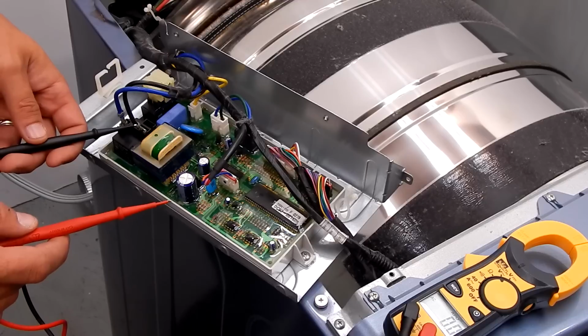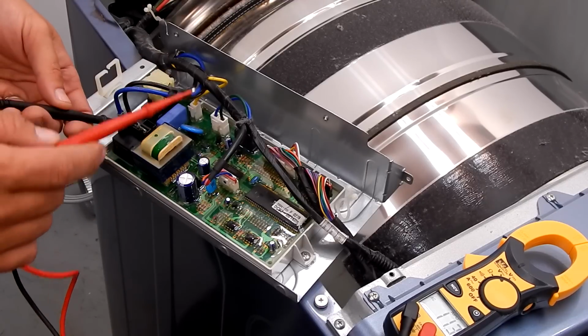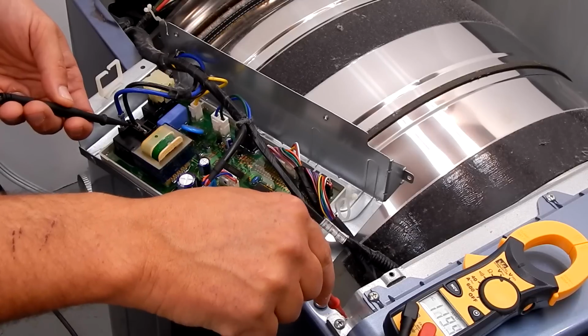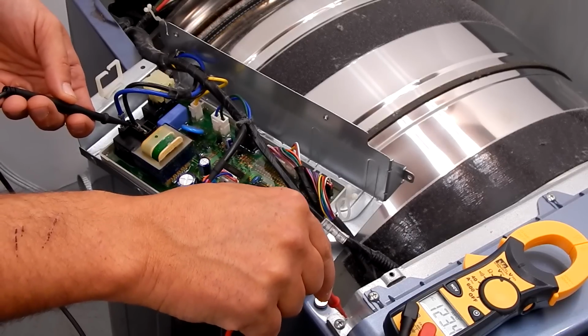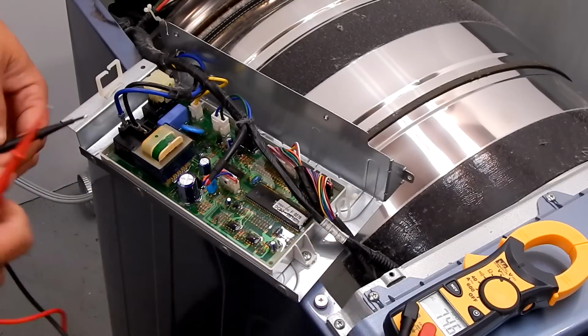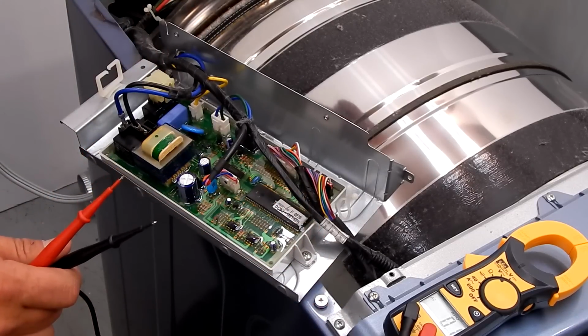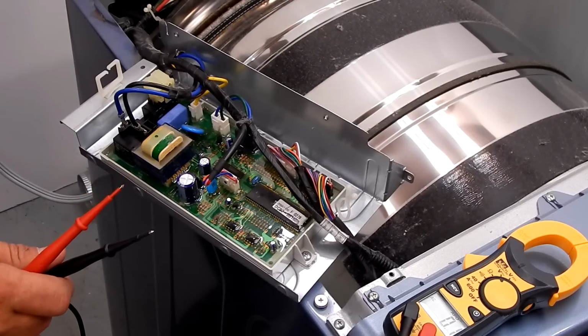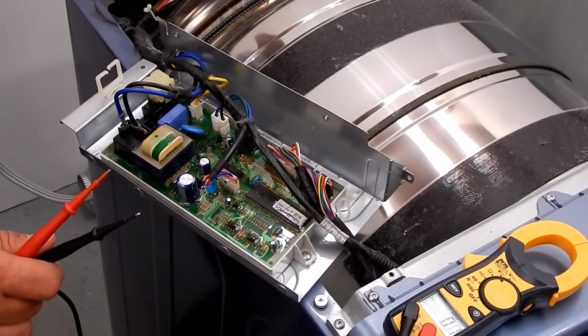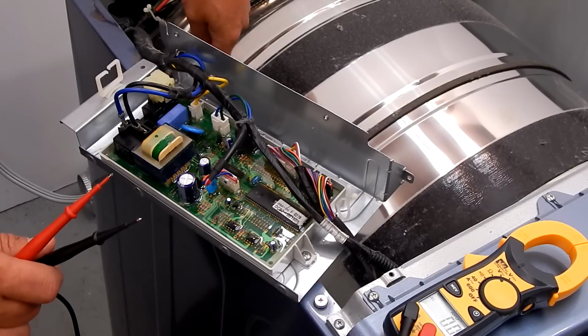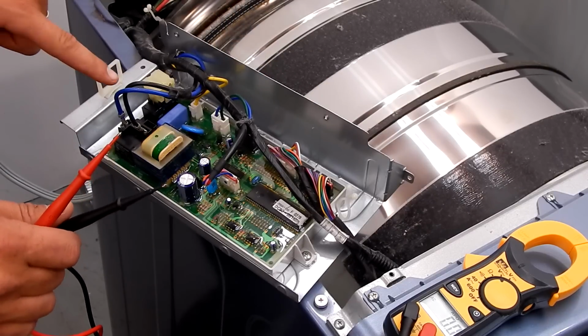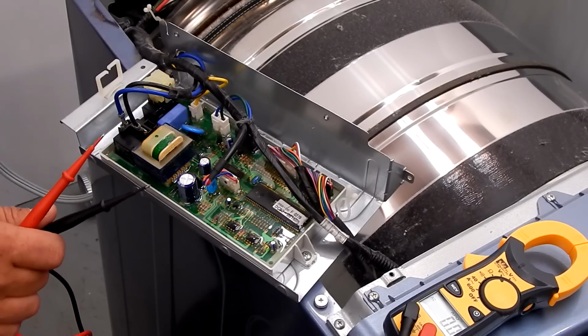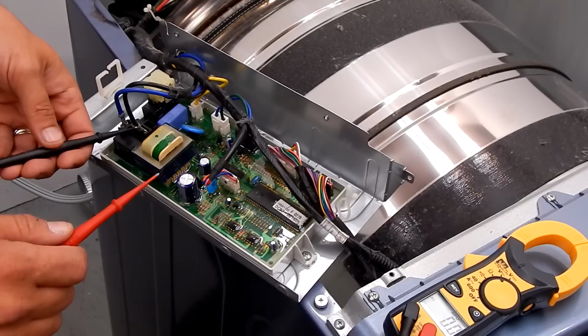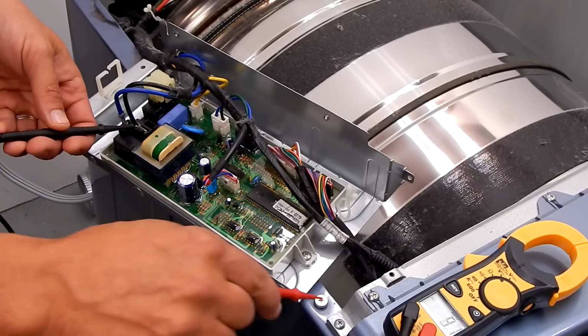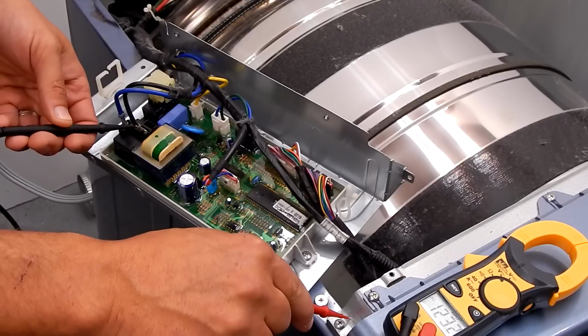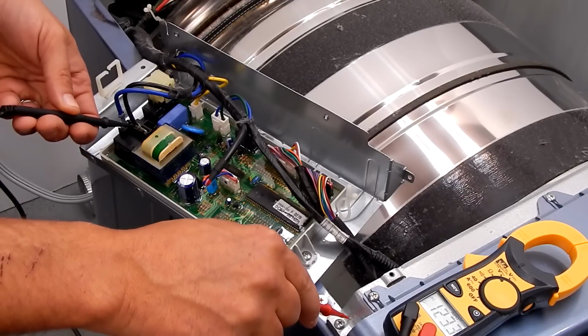But to test a relay, you want to go from the black wire, which runs over to the power coming in, and touch it on the ground. Now the meter's reading 120 volts right now, and that's what you're supposed to get. This relay is going to put the other leg of 120 to the heating element and the heating system, and the other leg of the 120 is already going down, so it makes a complete loop. So you need this other 120 to have 240 to the heater. So basically, the black wire is coming in to the frame of the machine. I don't know if you can see that meter or not, but we're getting 120 volts.